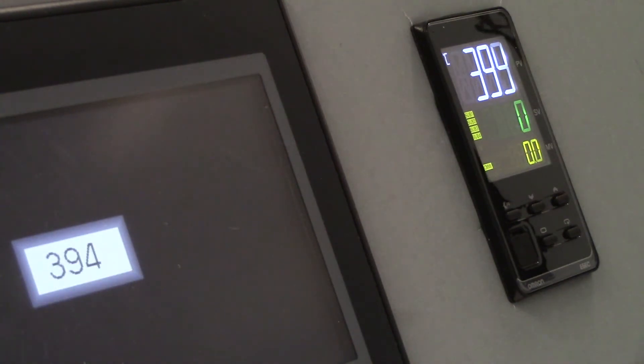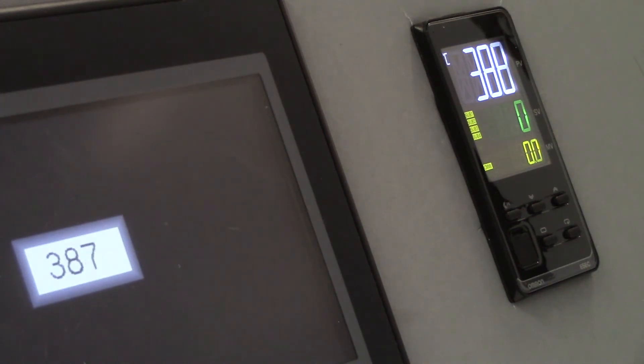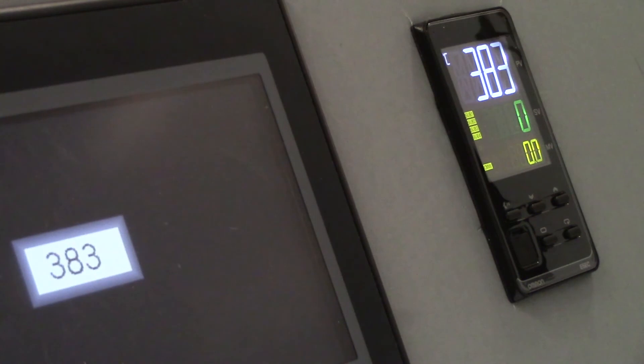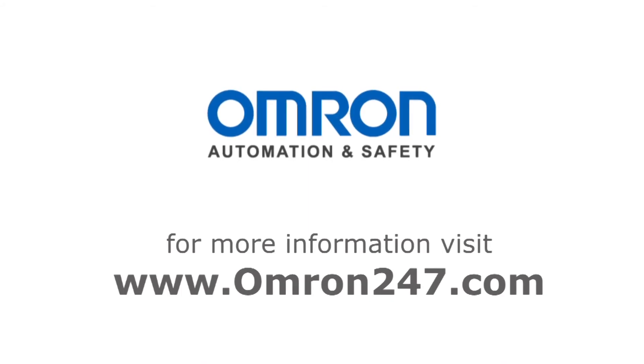Now that we're done, we press and hold the level key again for three seconds. The whole display will light up, and as you'll see, we have the two units communicating. I'll go and adjust the set point, and you'll see that it's tracking just fine. Thank you very much for your time. This ends the presentation for the E5EC to NB Touchscreen programming.